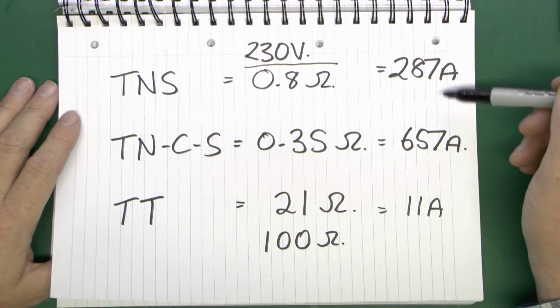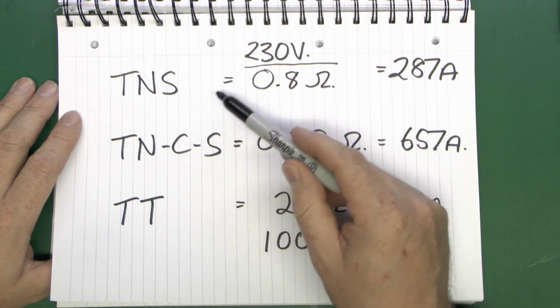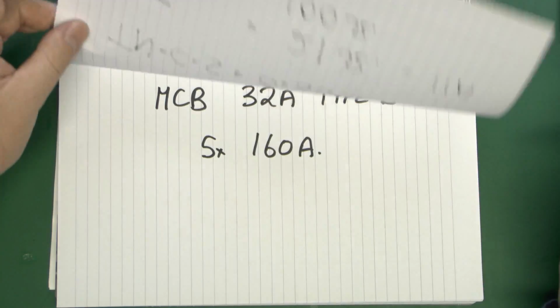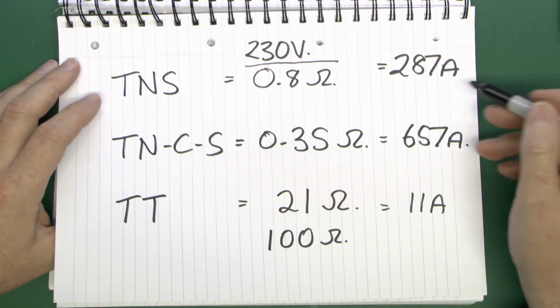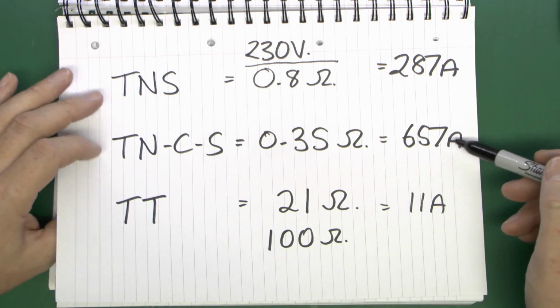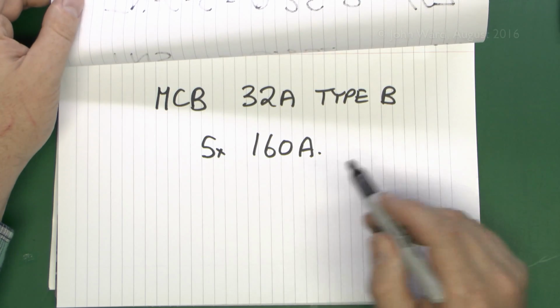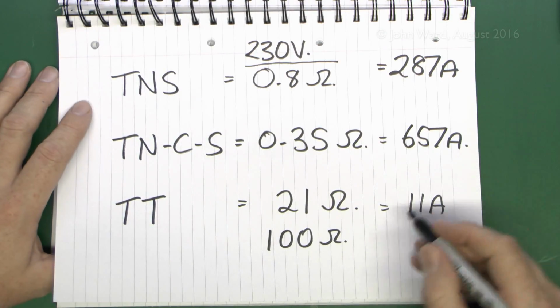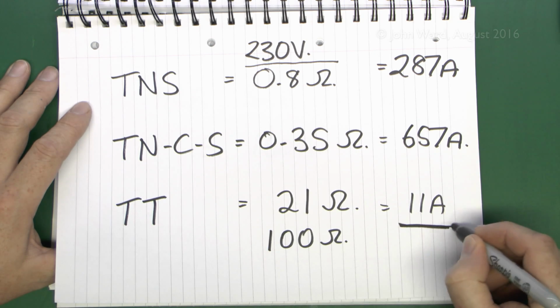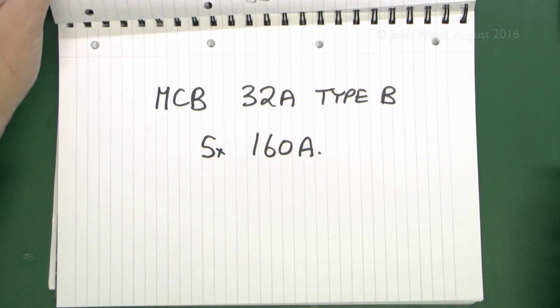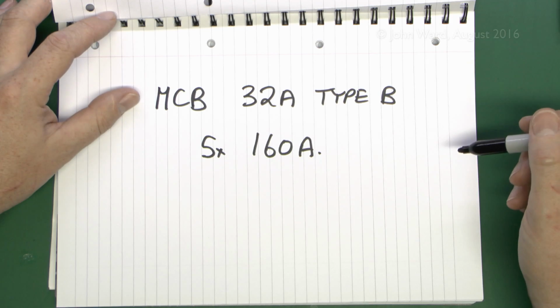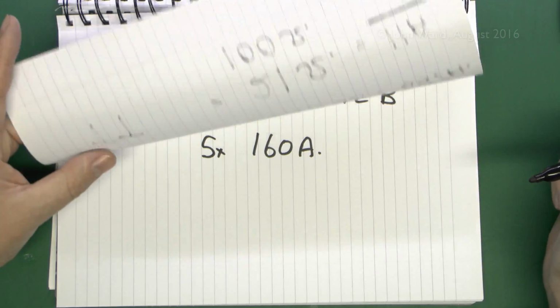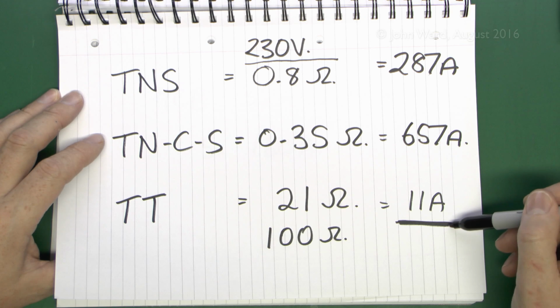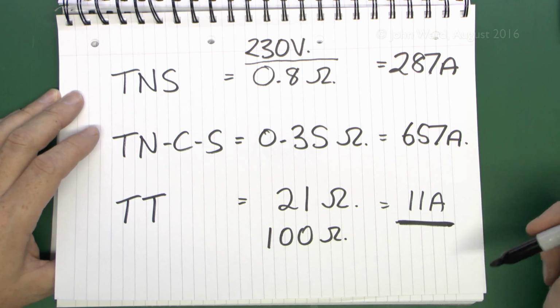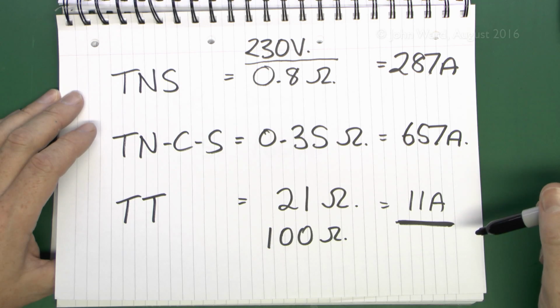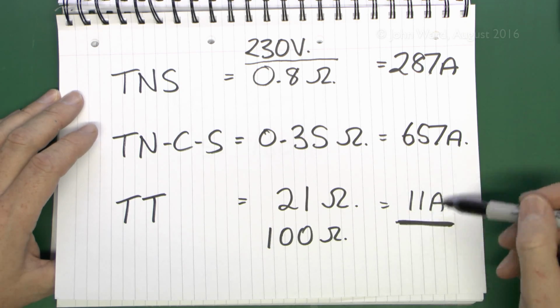So if we have a look over here, in all the cases, even at the lower count of 287, it's clearly a lot more than the 160, so that's absolutely fine. And again, 657 is obviously massively more than the 160, so no problem there. But on the TT supply, unfortunately the current available is only 11 amps. Pretty obviously, if you put 11 amps through a 32 amp circuit breaker, nothing will happen. So in this case you're going to need an additional device, which is generally an RCD or one of those old voltage operated leakage devices, to disconnect in the event of a fault to ground.